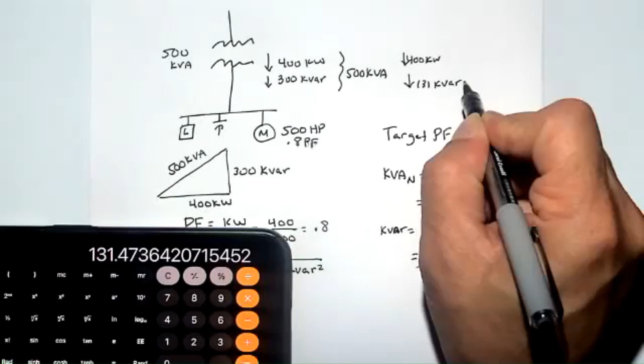What I have to do though is when I apply a capacitor here, I have to negate what's already there, which is 300. I have to get it down to 131. So that means I have to add a 169 kVAR capacitor. Well, we know we're not going to buy that, because it's just not a standard size. So what we're going to have to buy is a 150 maybe or a 200 kVAR.